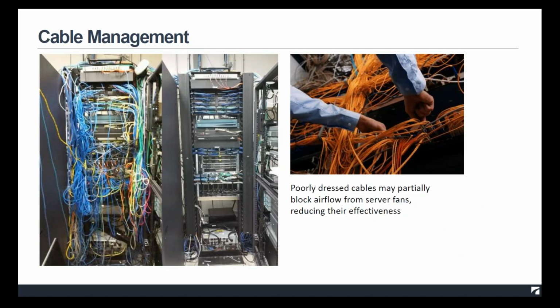Cable management. So Steve showed some pictures of underfloor cable management and above ceiling cable management. You should also think about the back of your cabinet. If you look at the cabinet on the left especially, you see the cables are all over the place, and that's potentially going to put some back pressure on the server fans, and they're not going to operate as well. So especially if your bypass air control is not perfect, you'll get more recirculation air if you have poor cable management and you're just not going to circulate air as well.